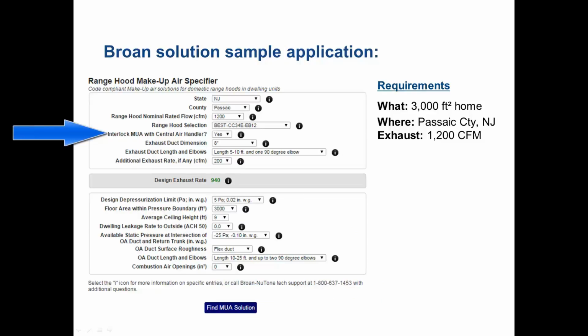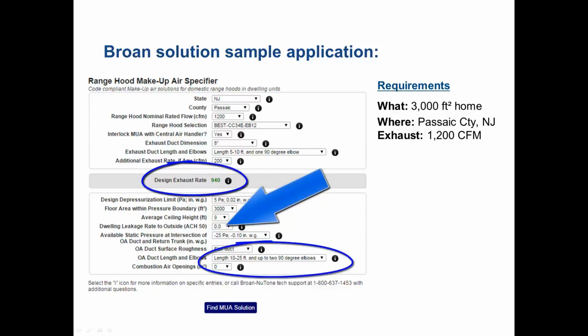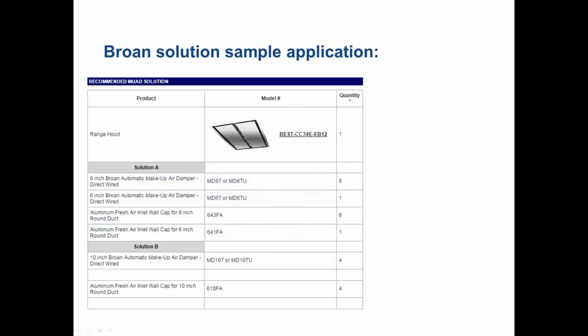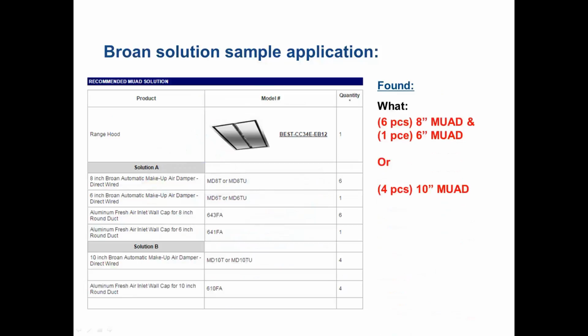We interlock the makeup air with the air handler to help the air in, have a short run of duct, throw in the exhaust for bath fans and dryer exhaust. Now notice that the design exhaust rate is only 940 CFM. No blower door test, and use a short length of flexible insulated duct. So what do we get? Lots of holes in the home. And don't forget, you could end up with 7 duct runs, 7 lots of cable to operate dampers if you choose electric dampers. That's a lot of installation.